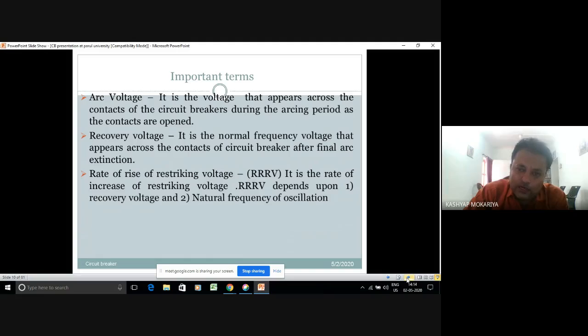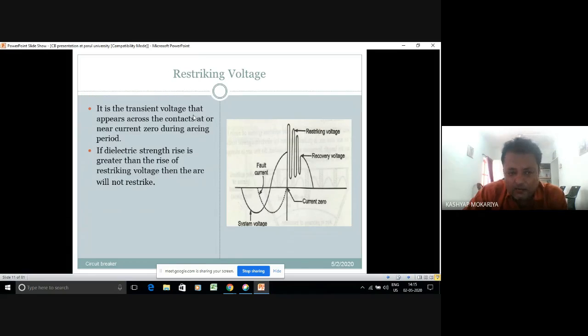Arc voltage is the voltage that appears across the contacts of the circuit breaker during the arcing period. Recovery voltage is a normal frequency voltage that appears across the contacts of the circuit breaker after final arc extinguishing. And RRRV is the rate of rise of restriking voltage, generally given in kV per microsecond. Now you can see here, what is restriking voltage? It is a transient voltage that appears across the contacts at or near current zero during the arcing period. You will see in my PPT that at this current zero this restriking voltage is there. Once this restriking voltage goes off, you get the normal frequency voltage, that is your recovery voltage.